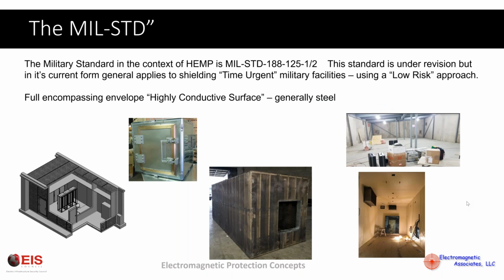Basically, when you're diving into this, you've got the MIL standard to guide us. That's really the first document that's out there to help evaluate this. And the military has been doing this for a number of decades, and that's embodied under the MIL standard 188-125-1-2. 1 is for fixed facilities, 2 is for mobile, and Kevin Poole will be talking about some of the modular and mobile facilities in the next presentation. But this standard is presently under revision. It's been under revision for a while, but it applies to shielding time urgent military facilities. That's time urgent, just saying that you can't afford any disruption whatsoever, so you have to use a low risk approach to make sure that everything works.